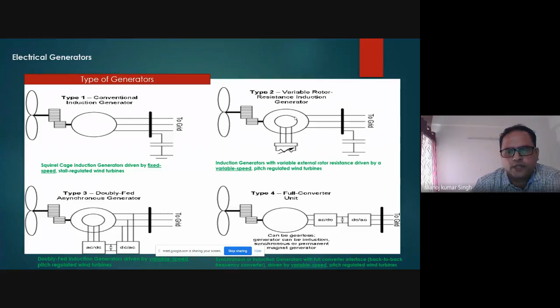So types of generators: type 1 is conventional induction generator and type 2 is variable rotor resistance type induction generator - these are old generators used in old turbines. Now in modern turbines, doubly fed asynchronous generators and full converter units, which could be used for both synchronous and induction type generators, are quite popular. So type 3 and type 4, meaning doubly fed induction generator and synchronous generator full type converter generators, are quite popular nowadays in wind turbines.